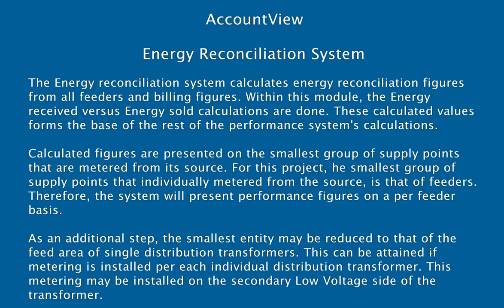Therefore, the system will present performance figures on a per-feeder basis. As an additional step, the smallest entity may be reduced to that of the feed area of single distribution transformers. This can be obtained if metering is installed per each individual distribution transformer. This metering may be installed on the secondary low-voltage side of the transformer.